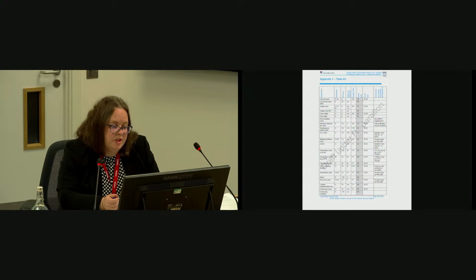I think the guidance is vague and subject to misinterpretation, so people might not have realised they needed a risk assessment or that they were derogating from anything. For the neutropenic patient ward that applies, but the general ward standard of 6 air changes per hour is very clear, so I'd have expected a risk assessment with that. There was consideration in an email trail around the renal outpatient clinics, so in certain low-risk settings it might be acceptable, but you'd still expect a risk assessment in place for that decision.